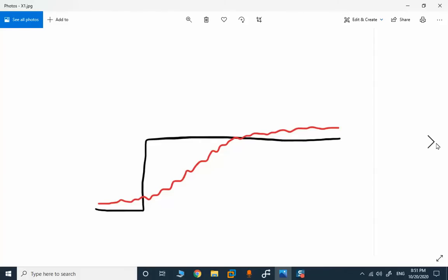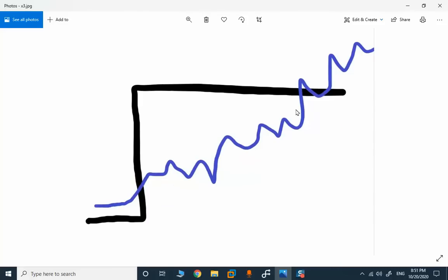It's possible to estimate and tune process models with these little oscillations or fluctuations, but in a case such as this, your chance is very low. You need to make your process stable by adjusting or repairing the positioner or your measuring transmitter, because you are at a constant command, and the PID controller has no role in this oscillation. It's in your process and your instrumentation.